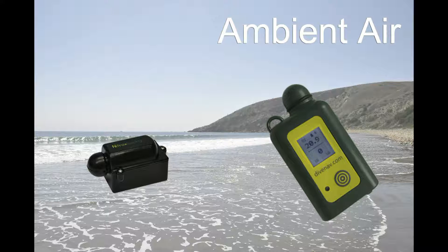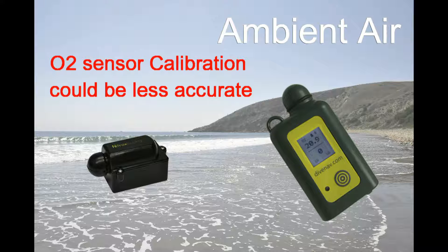Ambient air is the most available reference gas, but performing an oxygen sensor calibration using ambient air could produce less accurate results, as the temperature, pressure, and humidity of the ambient air could be quite different than the ones of the gas in the tank that needs to be analyzed.